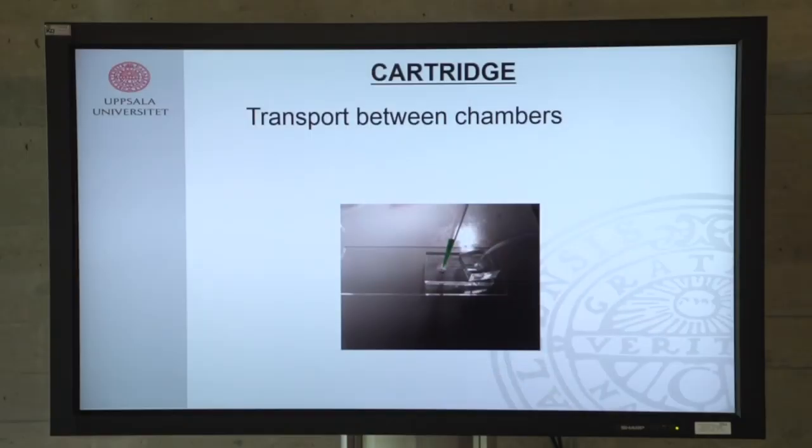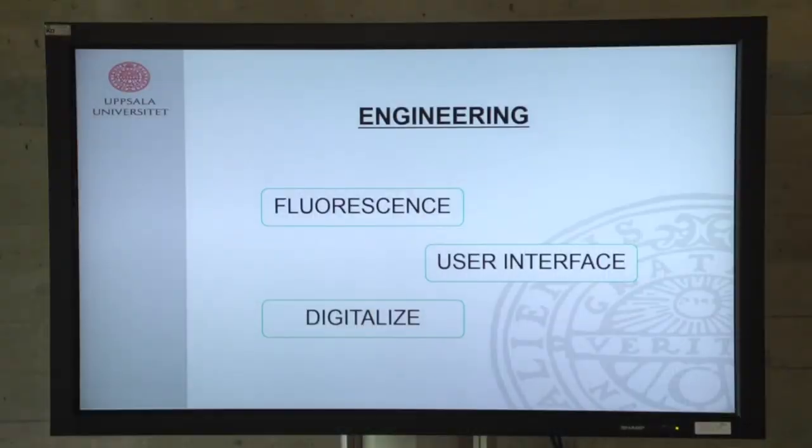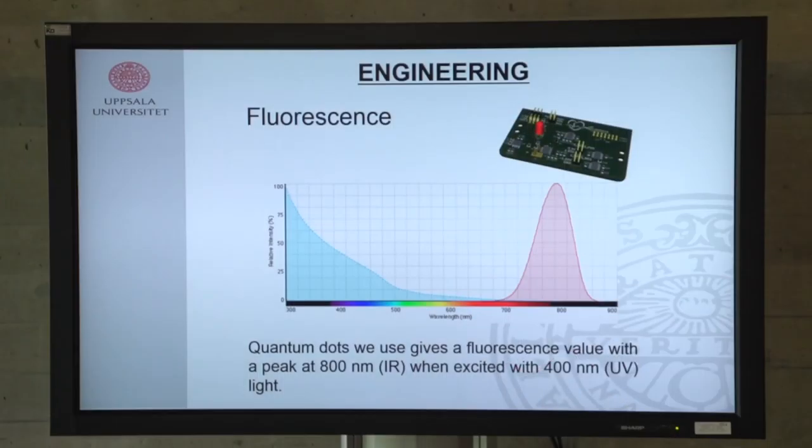Once this is done, we introduce the cartridge into the reader. The reader handles the engineering work — it deals with the fluorescence, digitalizes the signal we get, and quantifies it to give us the NT-proBNP concentration. We are using fluorescence as our signal, which comes from the quantum dots.